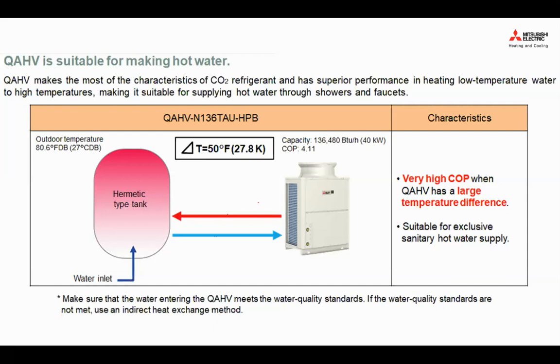So the COP is, and that's where it really accelerated. So very high COP when you have a large delta T, and then it is suitable for a sanitary hot water supply along with others. But the easiest way is perhaps, let's imagine you have cold water from the city starting at, let's say, 10 degrees Celsius, and the unit will be able to boost it all the way up to 70 degrees or even 77, 80 degrees C, depending on the usage. And then while maintaining that high COP level of 3.83, 4.11, depending on your delta T and depending on your outdoor condition.